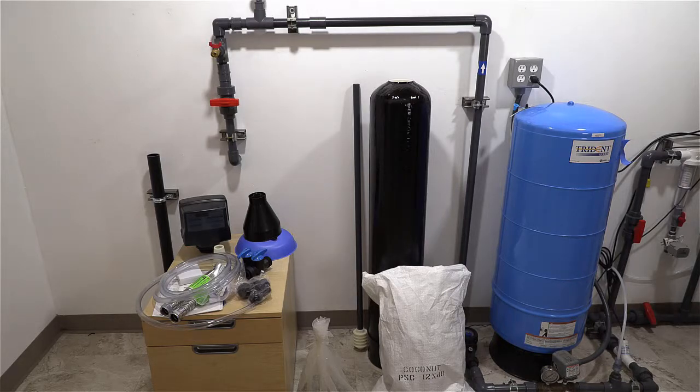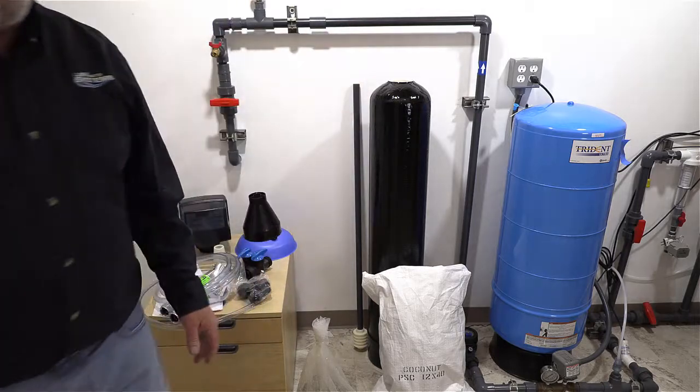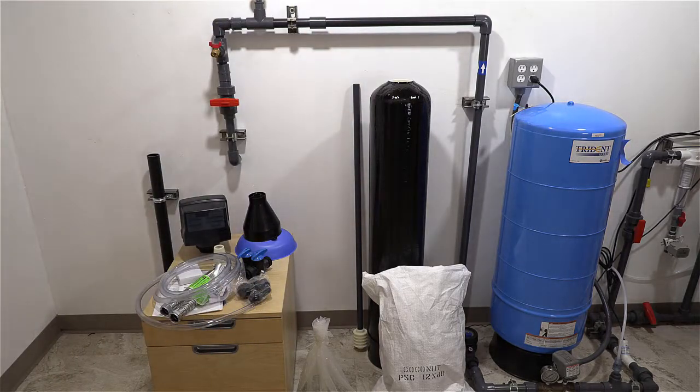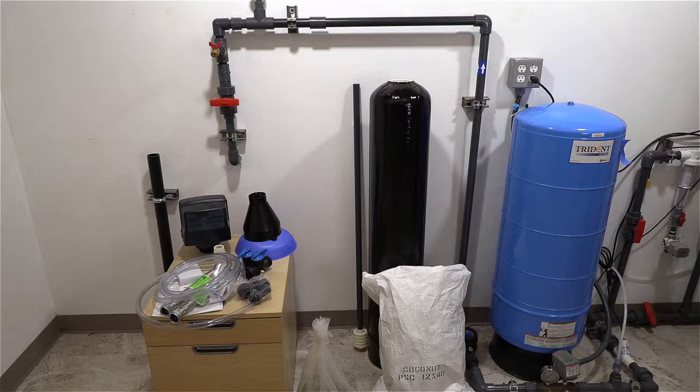For this demonstration we're going to install our system here. It's Schedule 80 PVC. Just a few things to keep in mind when you're going to install your system. You must be at least 10 feet from the entrance of your hot water heater, or you need to install a check valve there so the hot water has no way of getting back to it.